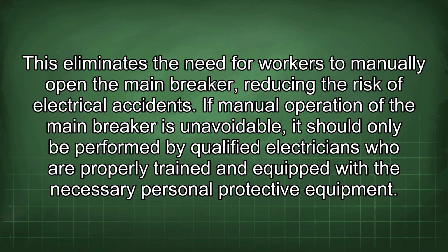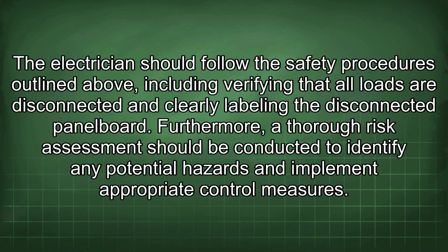If manual operation of the main breaker is unavoidable, it should only be performed by qualified electricians who are properly trained and equipped with the necessary personal protective equipment. The electrician should follow the safety procedures outlined above, including verifying that all loads are disconnected and clearly labeling the disconnected panel board.